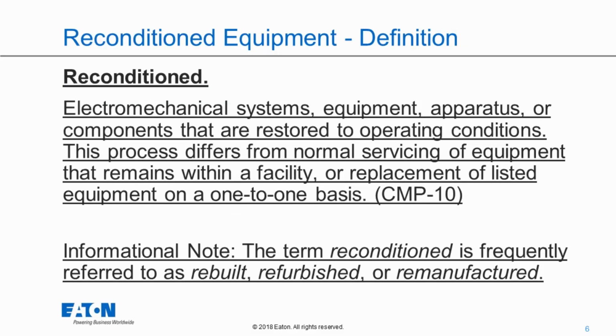In 2020, we added a definition of recondition, and again, this probably will need some work. As of the 2020, the definition of recondition is electromechanical systems, equipment, apparatus, or components that are restored to operating conditions. This process differs from normal servicing of equipment that remains within a facility or replacement of listed equipment on a one-for-one basis. The real challenge here is, what is normal servicing? What is maintenance, for instance? Hopefully that will be further clarified in the next edition of the NEC. They also added an informational note that the term recondition is frequently referred to as rebuilt, refurbished, or remanufactured.